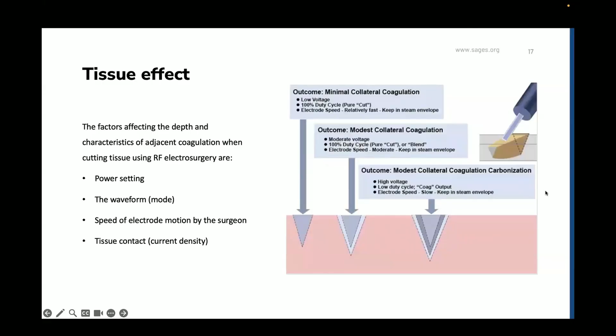And if you put this kind of on a scale, if you go low voltage, you use 100% duty cycle, which is your pure cut, and you're moving fast through tissue, you'll get the least amount of tissue thermal spread, and you'll only cut the tissue that is right at the tip of your instrument. Whereas on the other hand, when you use higher voltage, or when you use a low duty cycle, such as in the coag mode, and you go slower, you still get the cutting effect, but you also get more thermal spread to adjacent tissue, which can be advantageous when you're trying to coagulate deeper structures, as long as you're doing it purposely and manipulating these factors.